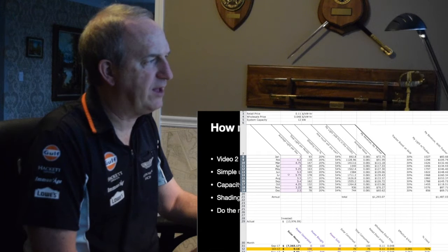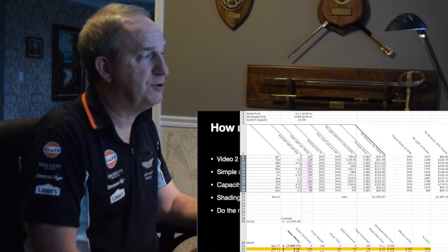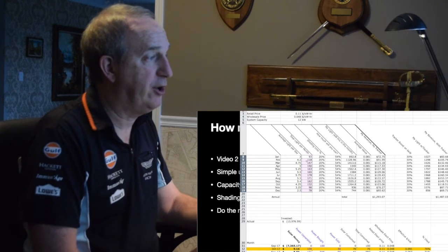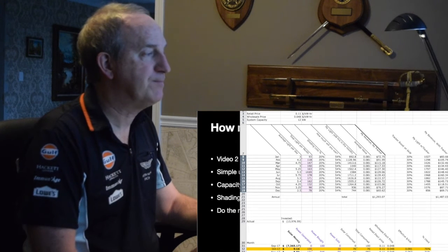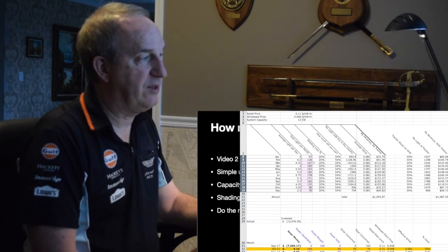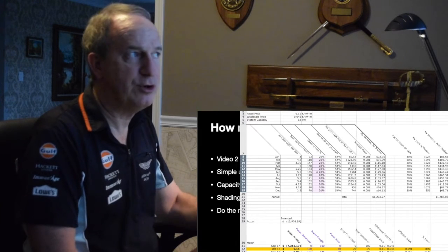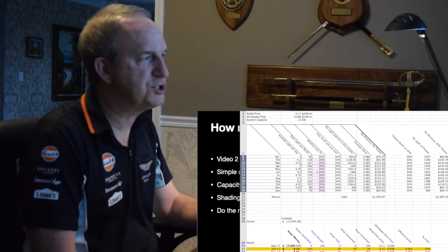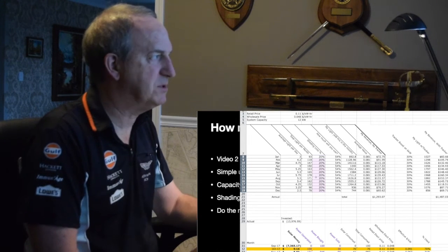And then you multiply that times the number of days, and for each panel, you should be able to generate 93 times its capability in January and 165 times its capability in the month of June. You need to discount that for shading, and shading does change over the course of the year. As the sun gets lower, you have a lot more shading, but I've just made it simple here.